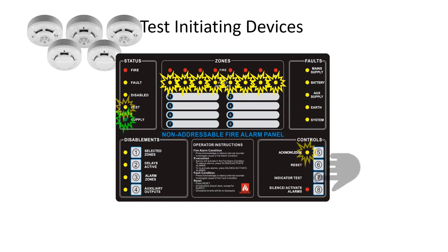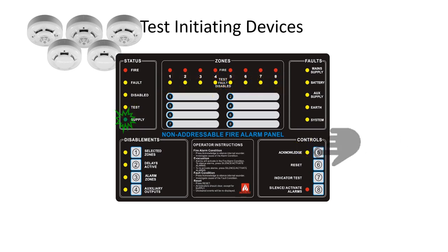At the completion of the test, and to exit the test condition, press the Indicator Test button. The Test LED and the Acknowledge LED will flash. Press the Acknowledge button to confirm. All the LEDs will be off. The control panel will remain in Access Level 3.